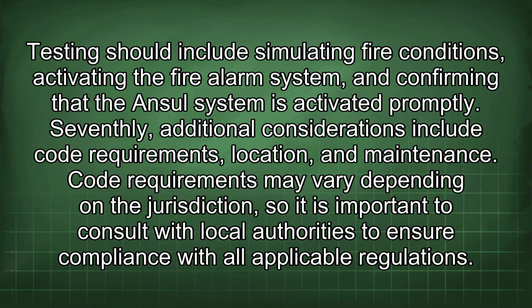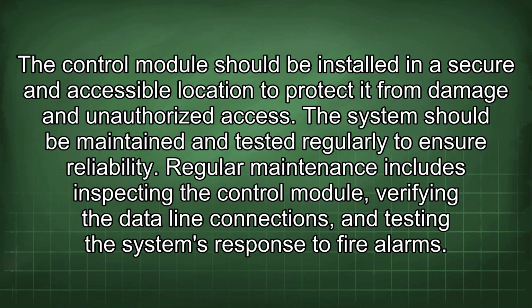Seventhly, additional considerations include code requirements, location, and maintenance. Code requirements may vary depending on the jurisdiction, so it is important to consult with local authorities to ensure compliance with all applicable regulations. The control module should be installed in a secure and accessible location to protect it from damage and unauthorized access. The system should be maintained and tested regularly to ensure reliability. Regular maintenance includes inspecting the control module, verifying the data line connections, and testing the system's response to fire alarms.